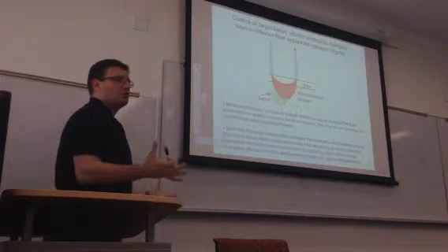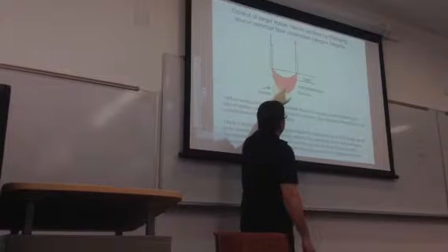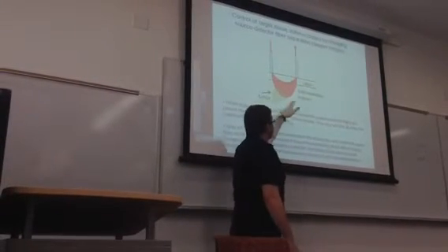But you pay a price for it too, because the deeper it is, the fatter the banana, so you're averaging more signal. Imagine you're only capturing a slice of a tumor, and you have a big banana that captures a lot of other stuff; the signal from the tumor will be diluted. So it's a compromise between big versus small. You don't want it to be too big, because then you will capture it, but you will also dilute it, and that's the issue of sensitivity. It's called volume averaging, or partial volume effect in imaging terms.